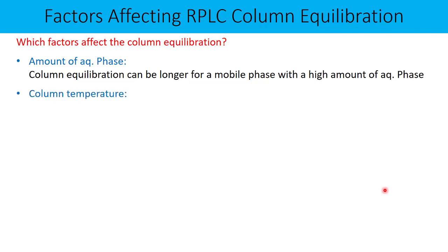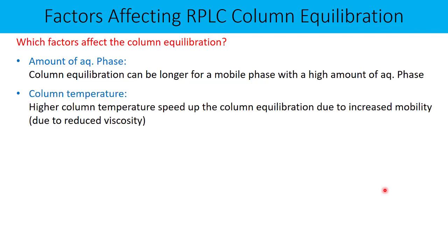The temperature of the column is also a factor. Higher column temperature speeds up column equilibration due to increased mobility of the mobile phase as its viscosity gets reduced. So if you want to achieve faster column equilibration, increase the column temperature above ambient temperature, maybe 30 or 40 degrees Celsius, and you will see a reduction in column equilibration time.